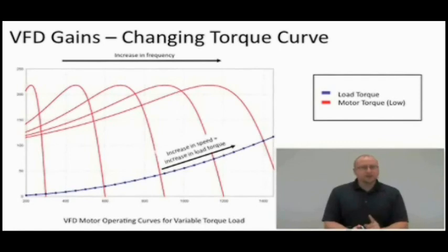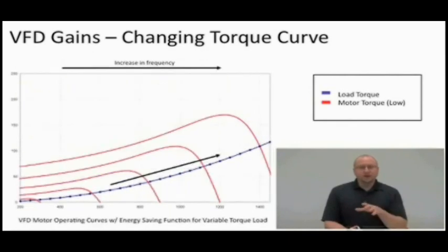But what is very interesting is if you look at this, for every speed that's lower than the base or design speed of the motor, the way that the load curve is shaped, the motor is actually very underloaded. And when the motor is underloaded, we'll explore this a little bit more when we talk about the next step, which is motors, it's operating very inefficiently. So one of the things that we can do is increase the efficiency of the system by changing those torque versus speed curves. And the way we can do that is with a variable frequency drive. It not only has the capability of changing the frequency, I can also change the voltage. So by changing the voltage versus the frequency output of my VFD, I can actually tailor that torque versus speed curve to more suit the application.